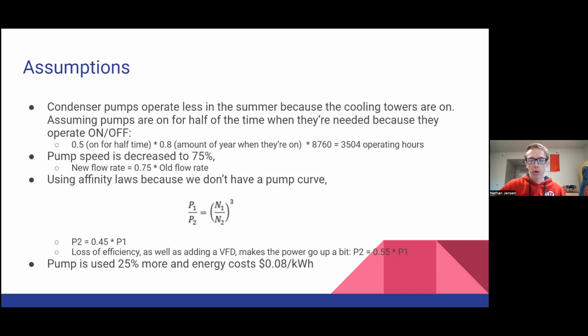Now, I think that the power equation that was shown previously is more accurate, but if you don't have all those, the flow rate and the pressure and things like that, you can use the affinity law and it still is a pretty good answer. And so here we assume that because adding a VFD decreases the efficiency, we're going to have about 55% of the current power will be the new power after implementing these VFDs, but the pump will be used 25% more.